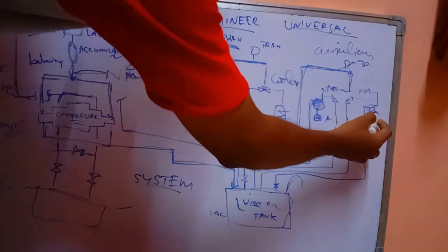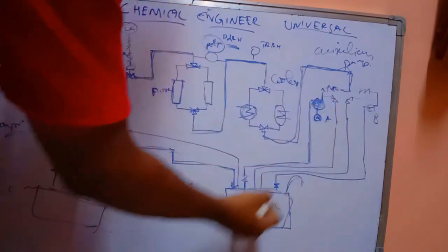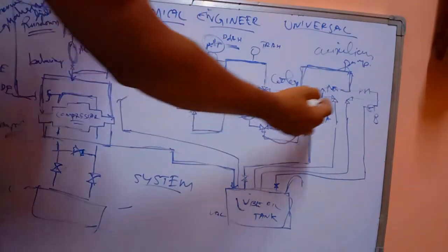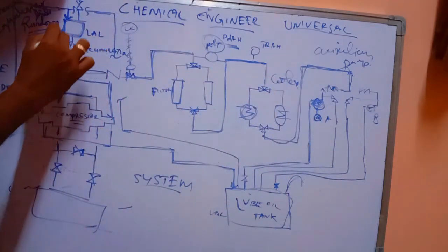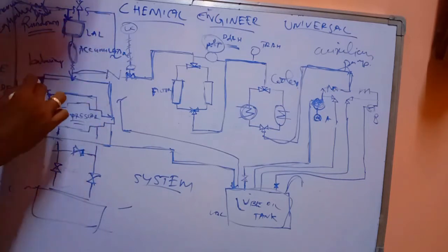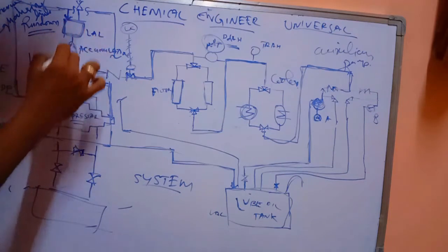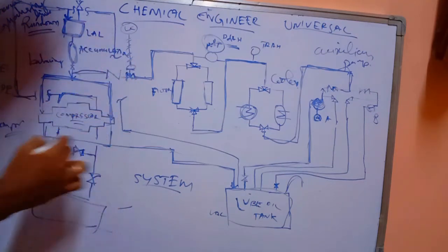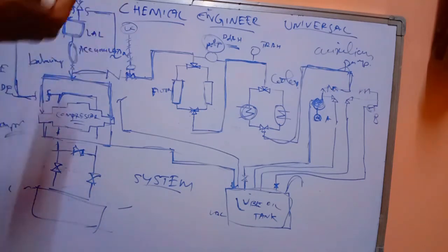So now we will see our interlock system and safety interlock system. The auxiliary pump started, is taking the oil, passing through the line. After the system is normalized, means this level is filled, by running the pump, this rundown tank level will be filled. After filling the level only, the compressor will start. The sequence will be like that only to protect the system from getting fault. So after the lube oil tank is filled, it is flowing through all the lines, and then it is returning to the column. So when the lube oil system is perfect, then only it will give permissive to start the main compressor. Then only we can start the main compressor.